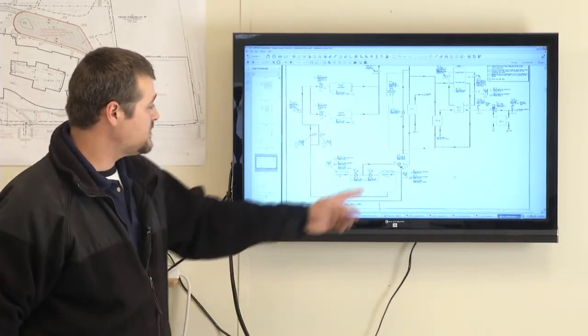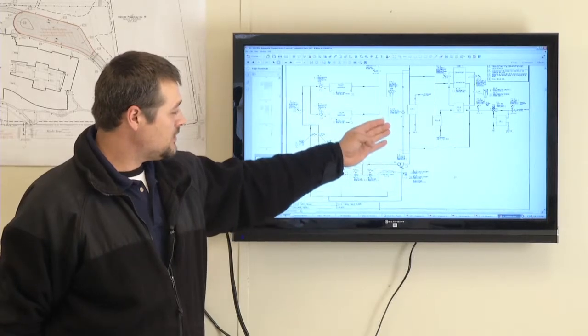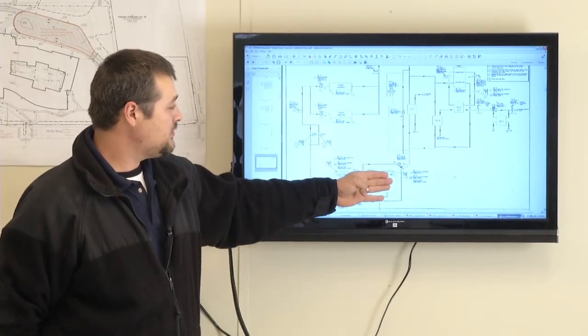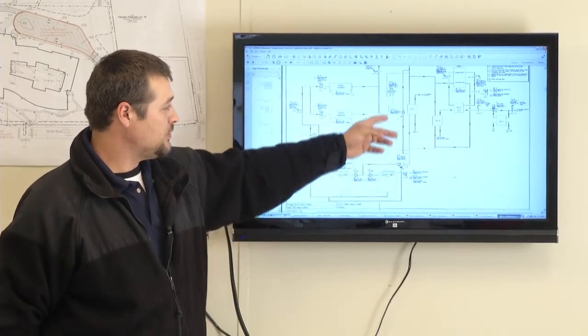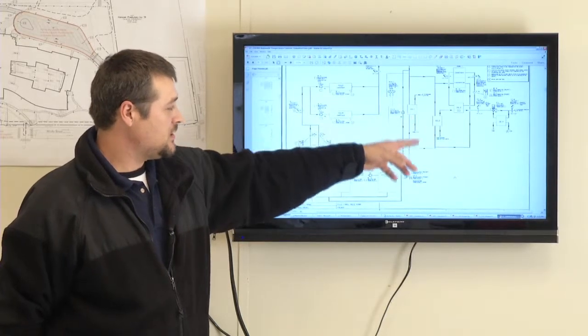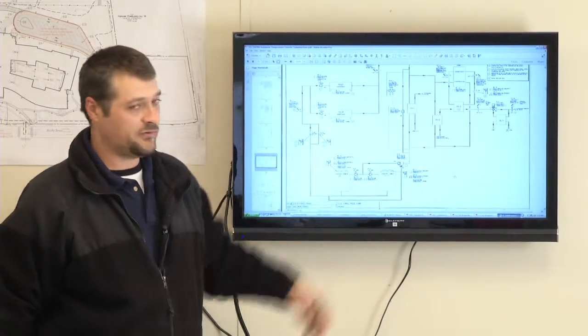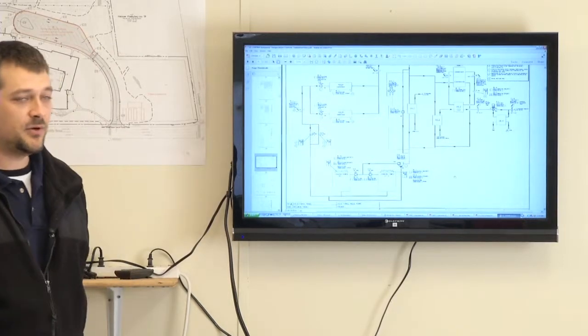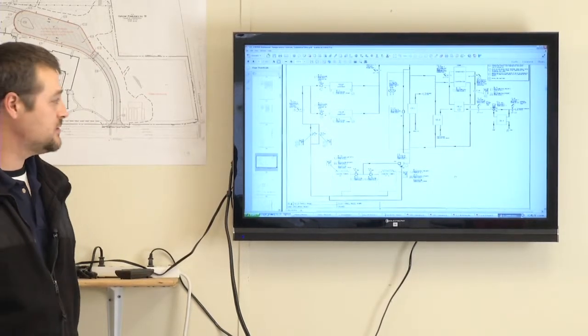The same with this two-way bypass. We don't want to cut our circulation completely off to the cooling tower, nor do we want to isolate just the heat exchanger loop with full flow. So that'll modulate, and we'll have limits in based on the balancer's recommendations.